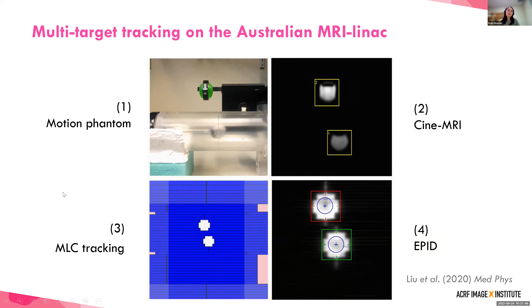So here I have a video showing multi-target MLC tracking in action. So you can see here, if we have 2 ball phantoms that are moving in opposite directions, we can image the targets and then send this information to the MLC controller to adapt the MLC leaves to each target's motion. So you can see here how we're adapting the different parts of the aperture independently for each target. So this particular video was taken on an MRI linac, but the same principle applies for application on a standard linear accelerator.